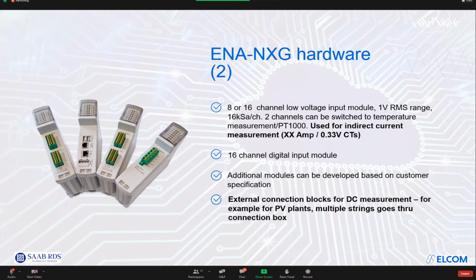Also, we can provide external connection block which can convert DC measurement. So if you have, for example, some photovoltaic plant and you want to measure the DC values going from the photovoltaic panels using the strings, and then you would like to measure also the AC values, for example, after the converter, you can use 1 meter, which can be measuring both AC and DC, and the DC should be measured using external connection block, which just converts the DC value to low voltage and then connect it to low voltage input module.